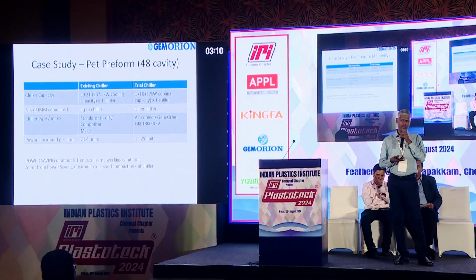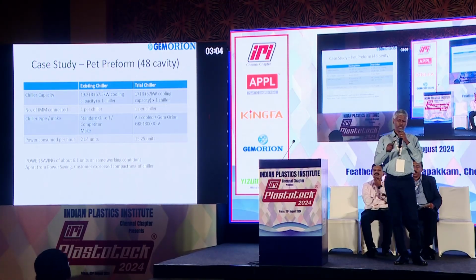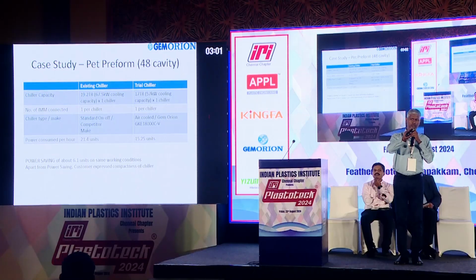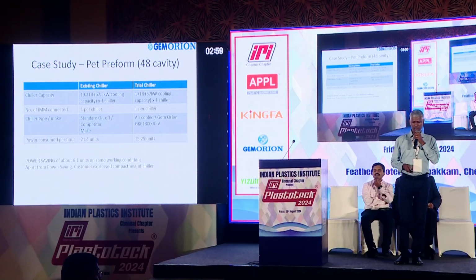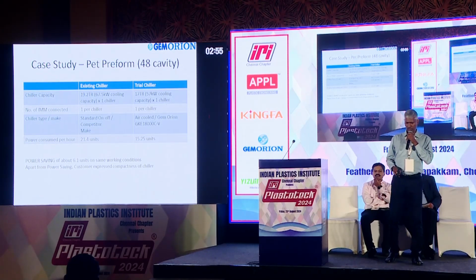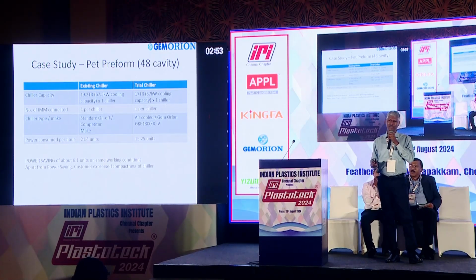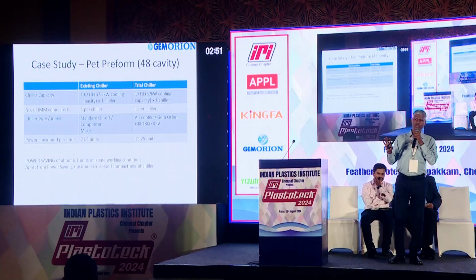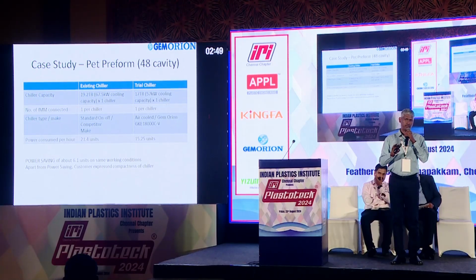If the chiller is big, the compressor is going to switch off, so the off time is going to be more and the on time is going to be less. In that way, we are pitching against a regular on-off chiller. So here we are able to get about 6 units, which is about 30% power saving. So 6 units per hour means about 4.5 lakhs per annum in saving in energy cost.